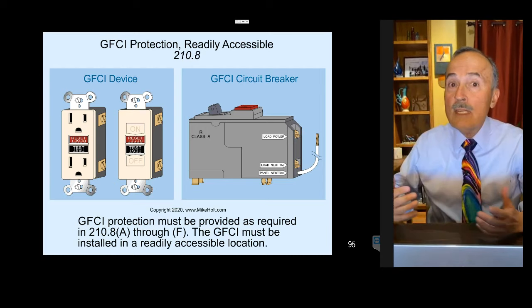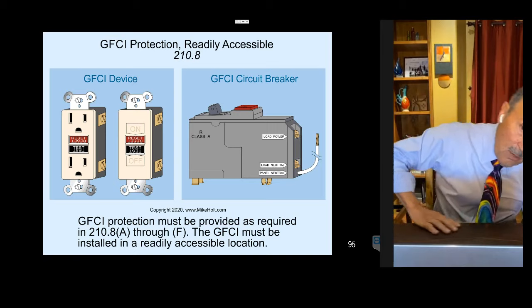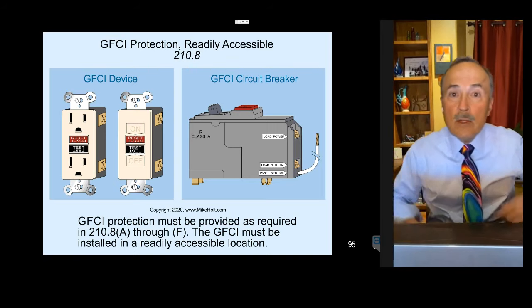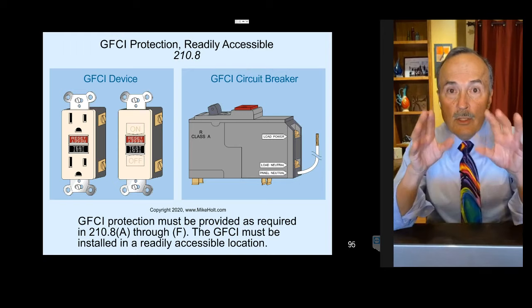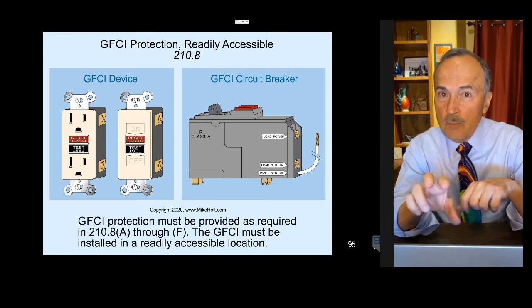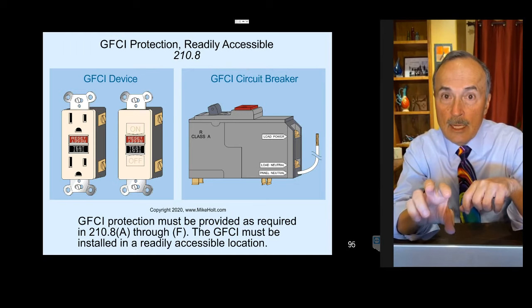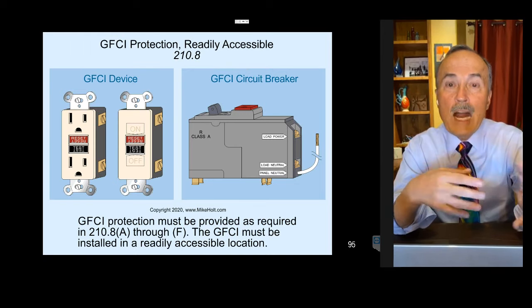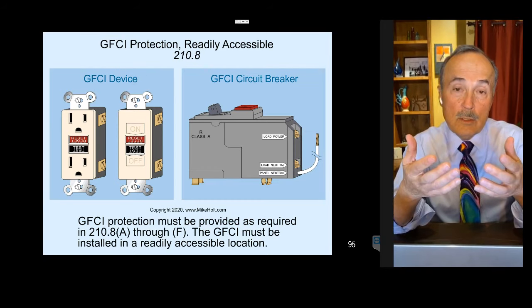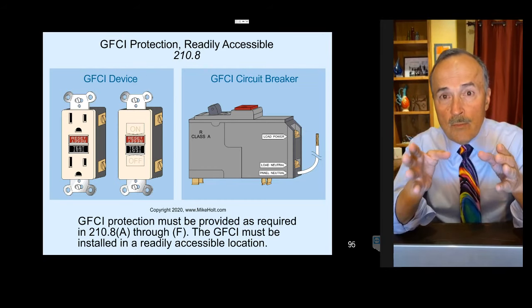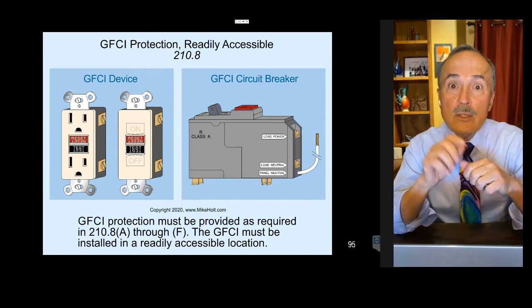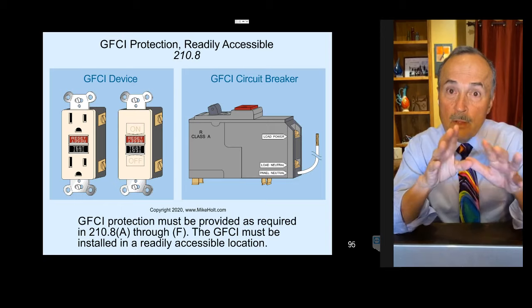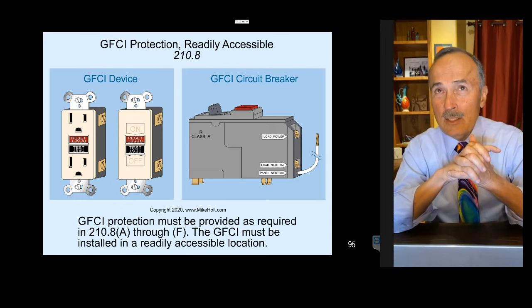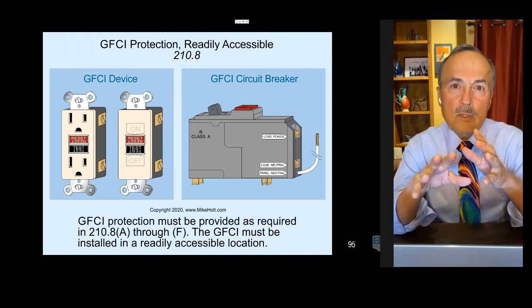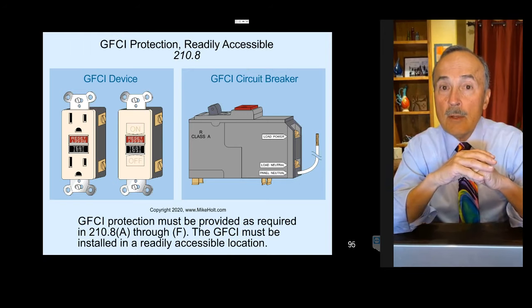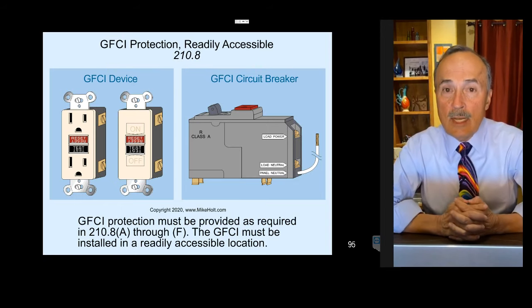Now you have to go to Article 100, read the definition of readily accessible, and it means that you can just kind of walk up to it. Don't have to climb over, don't have to get over this table to get to it. I don't need to get a 5-gallon bucket. I don't need a ladder. I don't have to get under the desk to get to it, like in a dwelling unit. You have your dishwasher disposal, your receptacle. You couldn't put a GFCI receptacle underneath the sink. Well, because you can't remove obstacles. If you have to remove an obstacle, well, then it would not be readily accessible. The intent of this rule of the GFCI to be readily accessible is so that people can test it monthly.